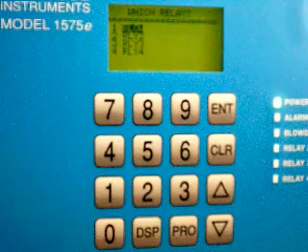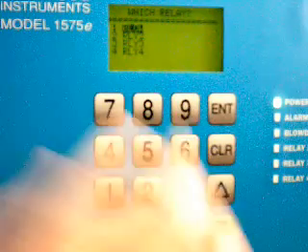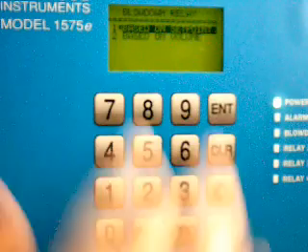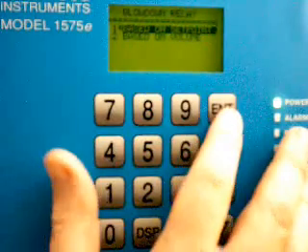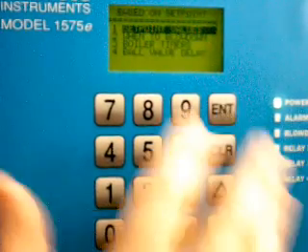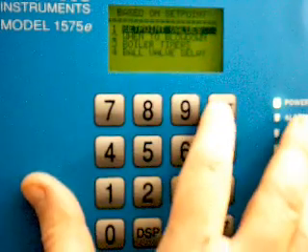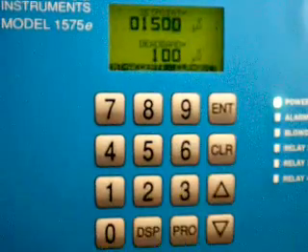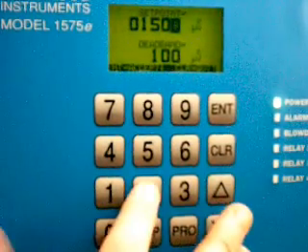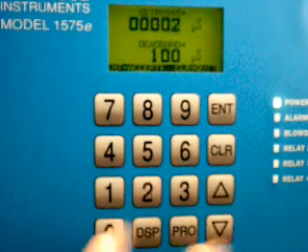The Blowdown Relay is the set point we're going to work with, so you can highlight Blowdown and hit Enter. We're going to go to Set Point, and now we're going to actually enter the set point number, which is item number one. In this case, I'm going to go ahead and change it to 2,000.